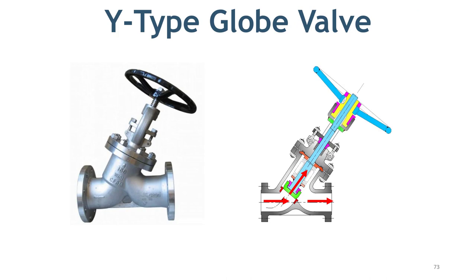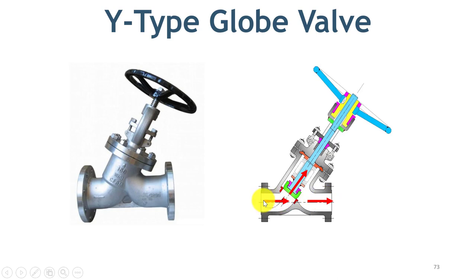Y-type body is the solution to the excessive pressure drop in T-type globe valve. Look at the body shape of this type of globe valve. Here you can see that the flow of the fluid only changes direction slightly, and the disc moves at a 45-degree angle, providing very little resistance to flow. This arrangement of body and disc makes the Y-type globe valve suitable for services where pressure drop is not desired. The shape of the body also makes it easier to identify this type of valve in the field.